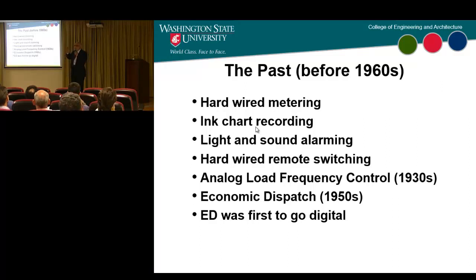So you had the pens, the wall of dials, and the other thing the operator needed to do was change things. The main thing changed was breaker closing and opening, and that also had to be done by hard wire. If you moved a switch mechanically, a hard wire sent that signal to the actual breaker in the field, and it opened up.